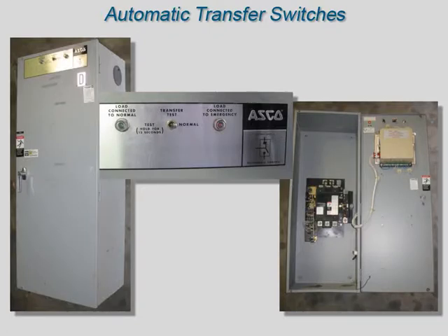Automatic transfer switches can be used to disconnect a de-energized secondary bus quickly from its normal power and reconnect it to a backup diesel generator. This ensures that a source of power will be supplied to essential loads under most circumstances. Automatic transfer switches are normally grouped into two categories: normal seeking and power seeking.